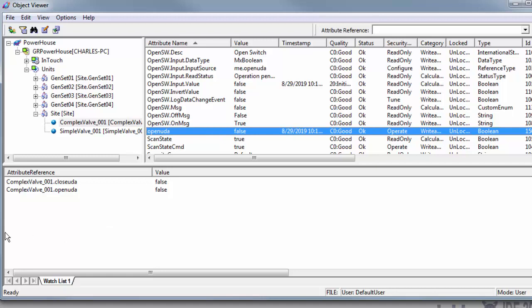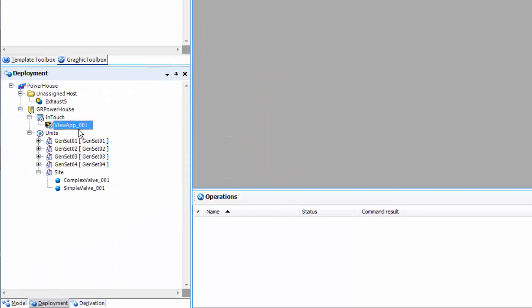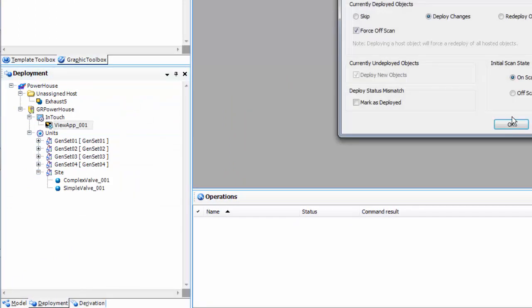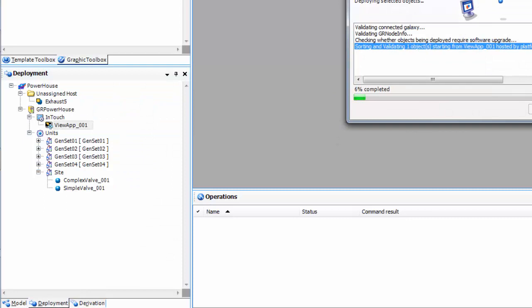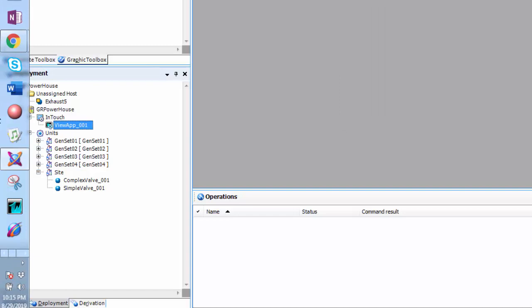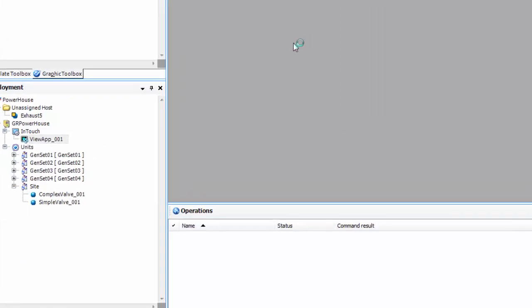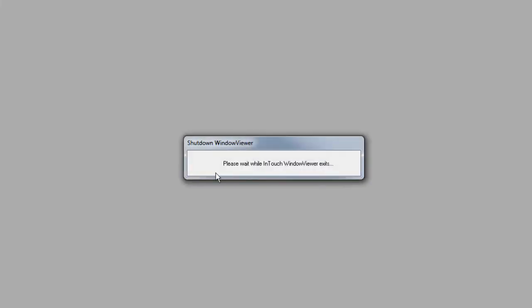They're both false so it would actually indicate trouble. We can verify that, but we're going to need to deploy our view app. So let's deploy our view app and then we'll go and verify that it is showing trouble. So both valves should be showing magenta. Let's run app manager and select the screen that has our valve on it. We might want to go put our valves on there first. I skipped a step.